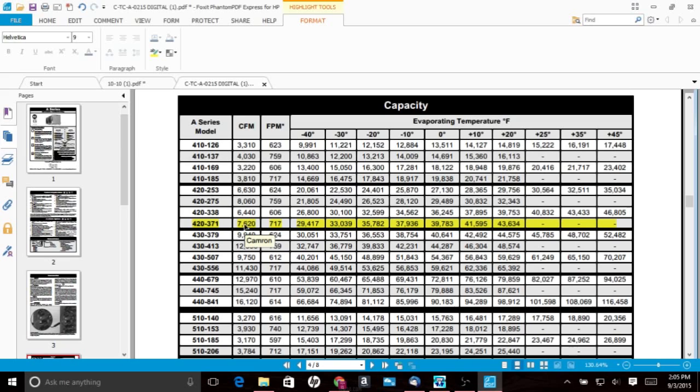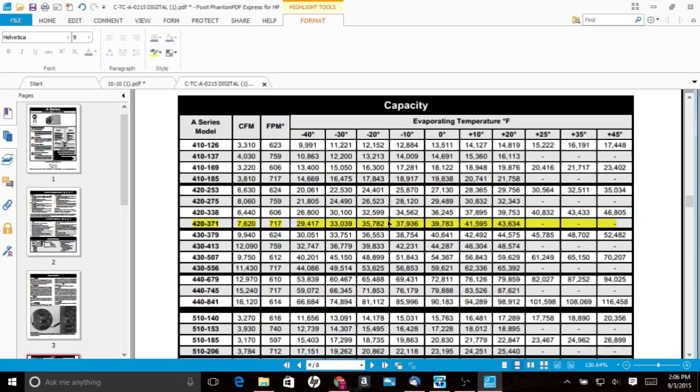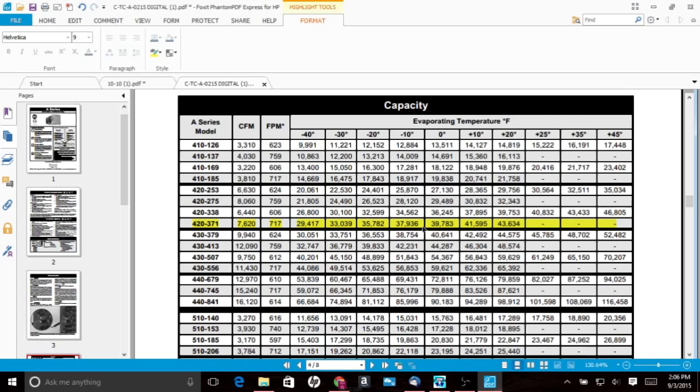And then we have our evaporator temperature. So in this case, the customer wants to maintain minus, or excuse me, zero degree box temp. Minus 10 to zero degree box temp is what they want to maintain. In order to do that, we're going to have an evaporator temperature that's at least 10 degrees colder than that. Typical construction is a 10 degree TD between the box temp and the evap temp.